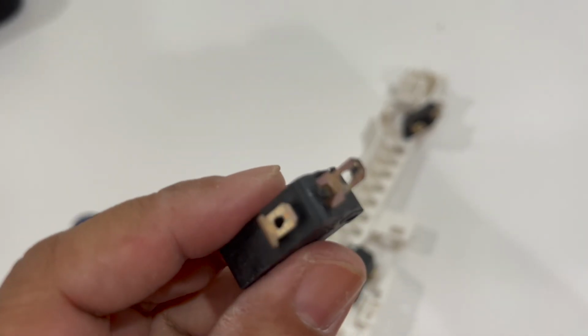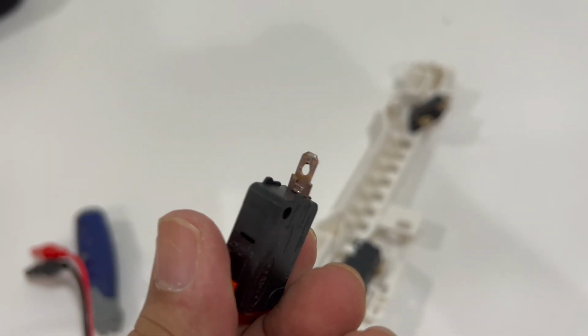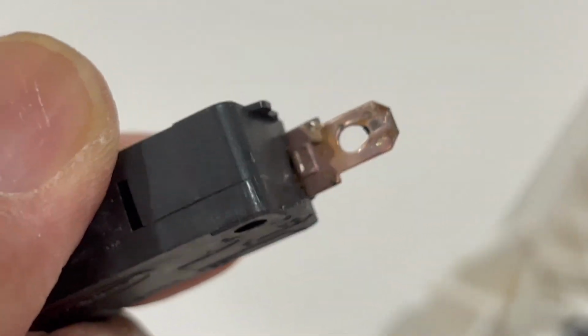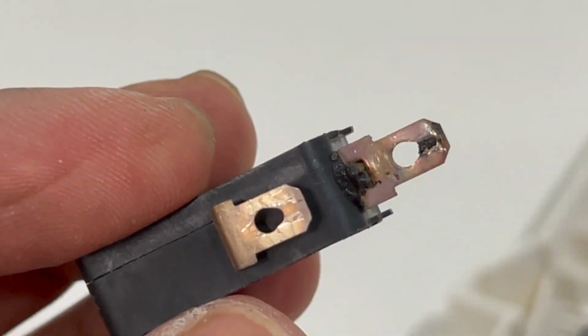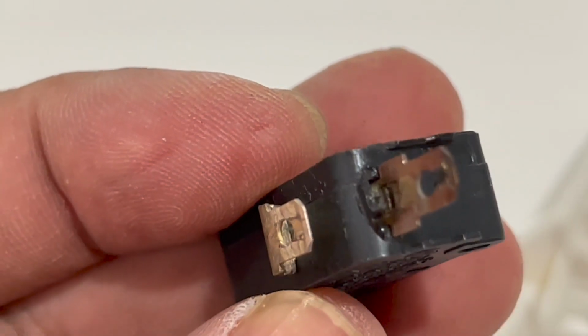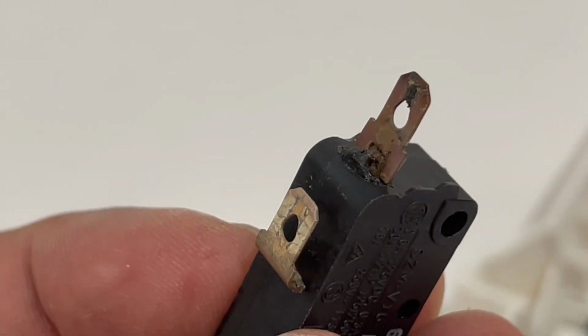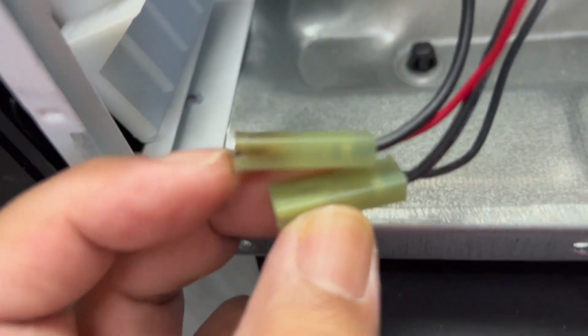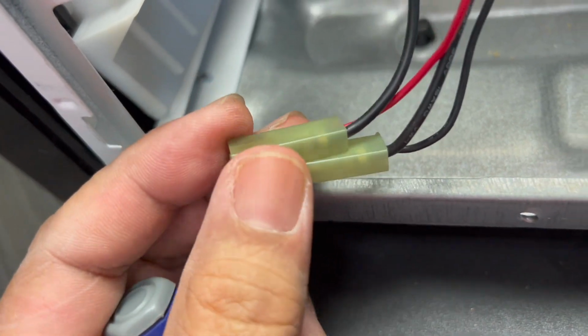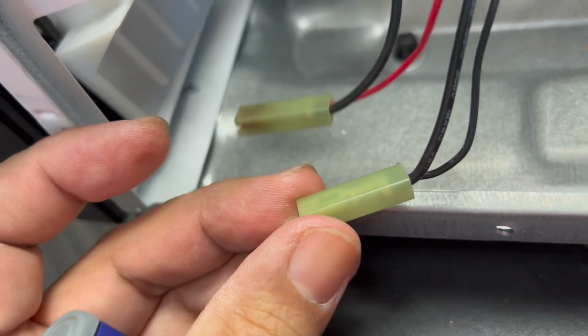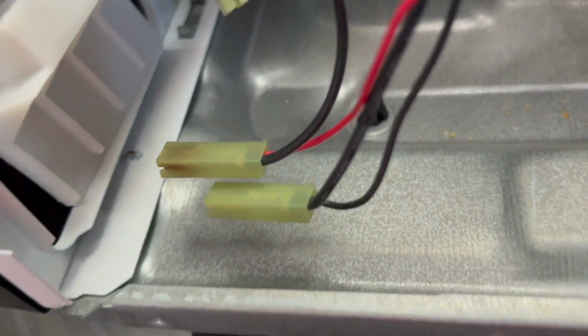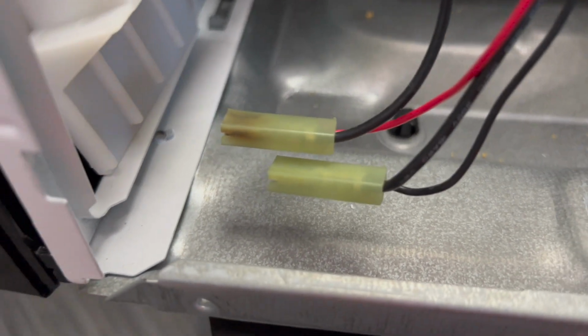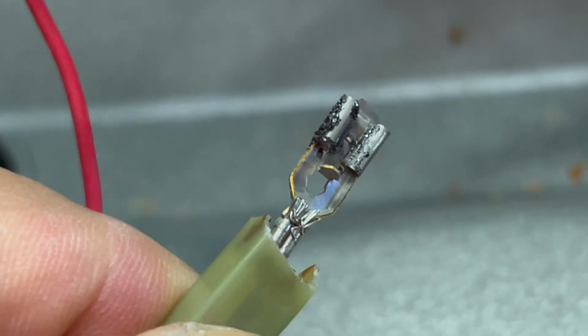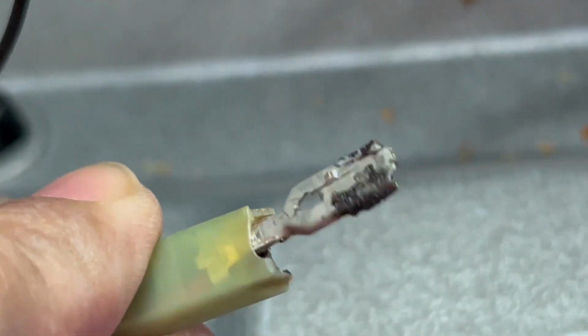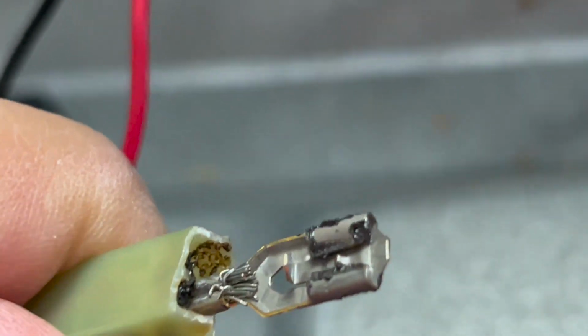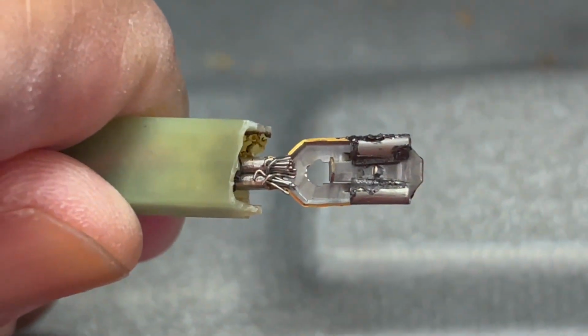The normally open terminal started arcing internally and produced a lot of heat, which started melting the housing. That heat also started to melt the sleeve on the connectors. You can see how one of them is darkened. The heat also compromises the connector itself, so change out the connector also.